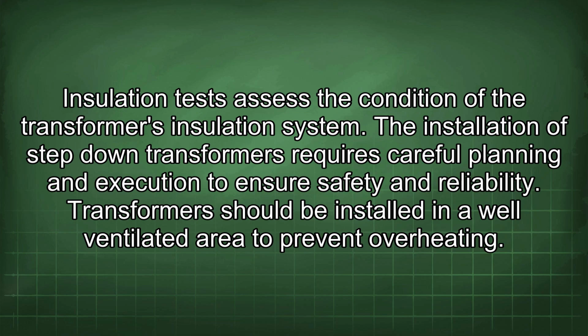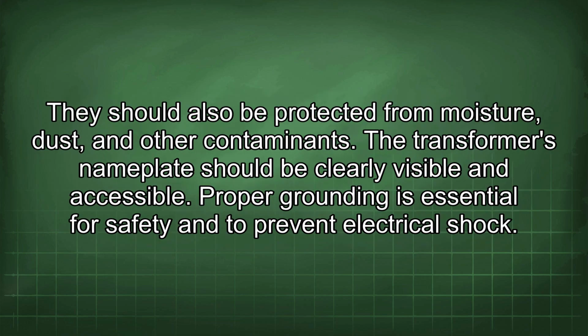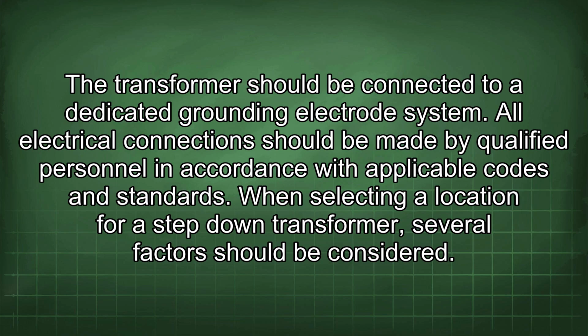The installation of step-down transformers requires careful planning and execution to ensure safety and reliability. Transformers should be installed in a well-ventilated area to prevent overheating. They should also be protected from moisture, dust, and other contaminants. The transformer's nameplate should be clearly visible and accessible. Proper grounding is essential for safety and to prevent electrical shock. The transformer should be connected to a dedicated grounding electrode system. All electrical connections should be made by qualified personnel in accordance with applicable codes and standards.